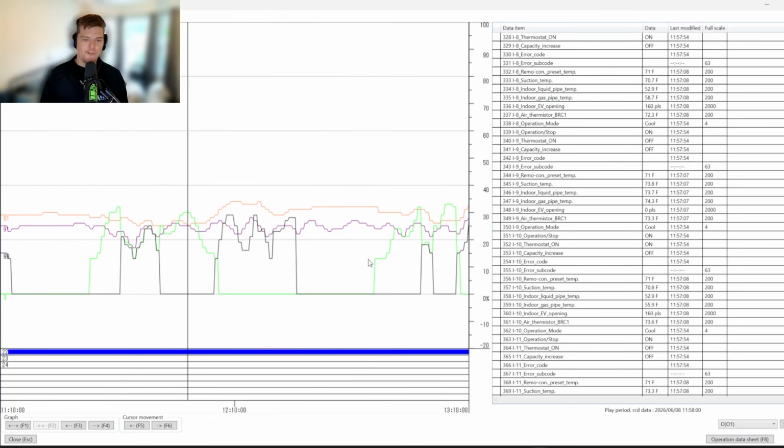All those things play a factor in troubleshooting VRF as a whole, but this is one of those things where you can look at it and know, okay, what is this doing? How is this changing? And I've even told guys too, where maybe they want the VRT turned on, and that's okay if that's your climate and it works for you. If you're there to stress test the system, I'm turning VRT off. I don't know about you, but I'm extremely impatient with systems like this. There's already enough startup control mode, pump down residual mode. Modes drive me crazy. I just want you to run the way I want you to run and stabilize so I can look at it.